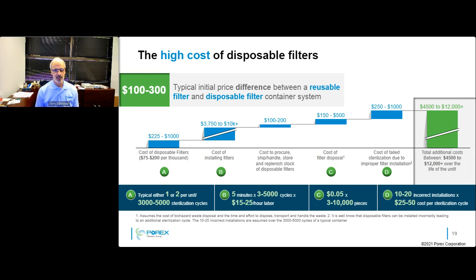Again, this is a really hard one to quantify, but it happens. Filters are installed improperly. Maybe it's reused. Maybe there was a tear in it because again, these are fairly fragile. They cut and tear very easily. Over the 5,000 cycles, if you just assume 10 to 20 of them are done incorrectly, you have to go back through the re-sterilization process, and it costs you maybe $25 to $50 to go through that process. That's another $250 to $1,000 of cost over the life of the container.